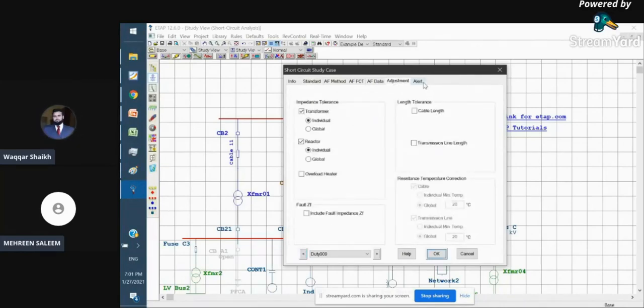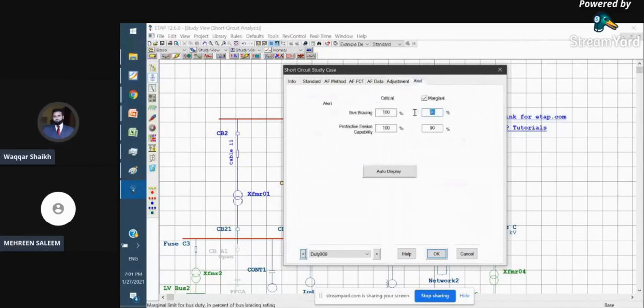Again here he's giving you options like marginal alerts, you have to keep at 90%, and critical alerts at 100%. Let me give you an example. If there is a bus bar of 50 kiloampere short circuit withstand capability, and this 50 kiloampere rated bus bar is expecting a fault current or prospective short circuit current of 55 kiloampere...